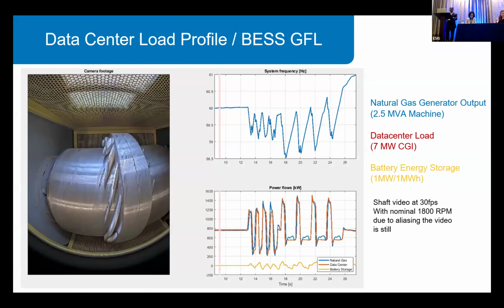Let me orient you to a video I'm about to play. The left side shows the rotor of the generator, which is rotating at 1800 RPM, while the camera runs at 30 frames per second. Ideally, if the rotor is just doing 1800 RPM it should appear still, since 1800 divided by 30 times 60 works out evenly. But if there are oscillations, you can actually see them on the system.